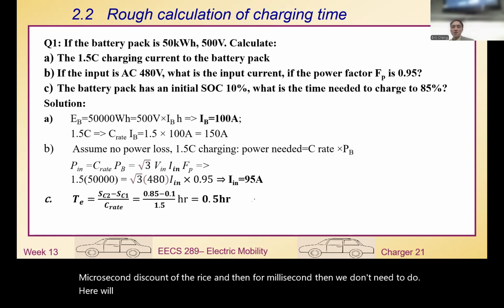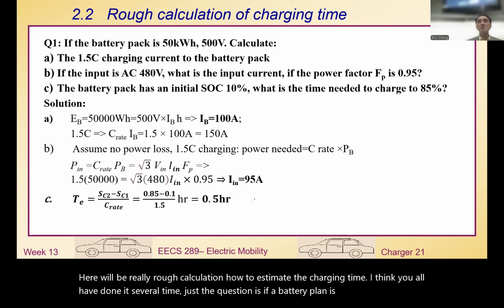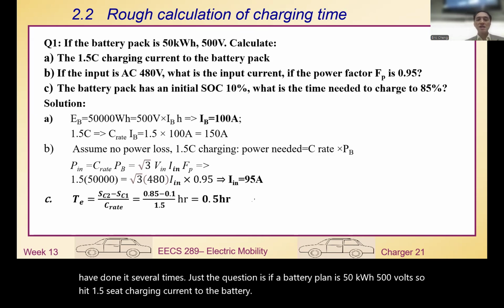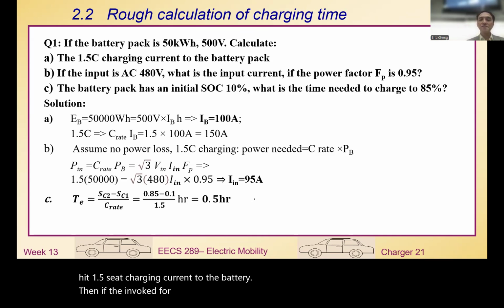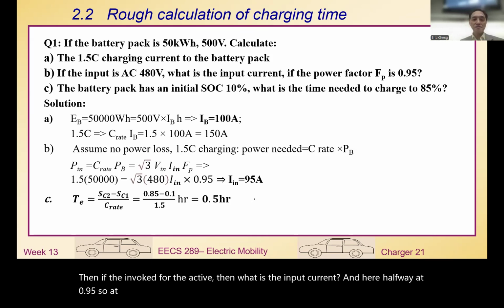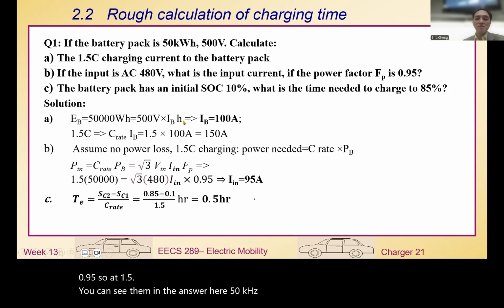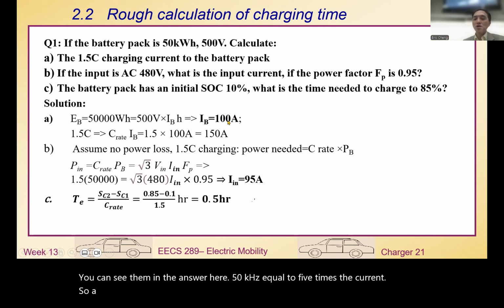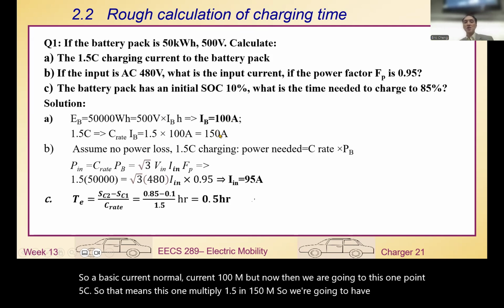Here's a rough calculation of how to estimate charging time. Suppose a battery pack is 50 kilowatt-hours, 500 volts, and we charge at 1.5C with an input voltage of 480 volts and power factor 0.95—what is the input current? At normal 1C, 50 kilowatt-hours equals 500 volts times current, giving a base current of 100 amps. At 1.5C, multiply by 1.5 to get 150 amps charging current.